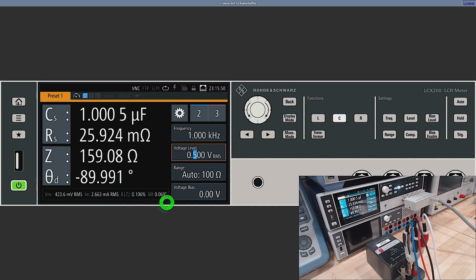Look at that. We've gotten a little bit worse. No change really observed here yet, but we can see that we're getting worse and worse. Let's go to 100 millivolts. Here's 100 millivolts. We're getting worse yet. A minor shift in the capacitance, and we can go all the way down to 10 millivolts RMS, and now we're beginning to drift a little bit away from where we were, and the confidence has gotten quite a bit worse as a result of that. But that's because we're now measuring 53 microamps RMS inside of the unit, and that is to be expected.